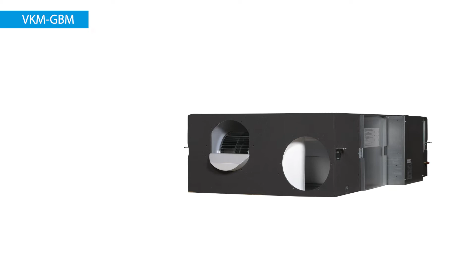Another product included in our commercial ventilation portfolio is the VKM GBM. It's also a made-to-stock standardized solution consisting of 3 sizes corresponding to airflow from 500 to 1,000 cubic meters per hour. It is a compact solution which in one casing contains the ventilation solution similar to what we saw in VAM, with a similar heat exchanger, a DX coil for heating and cooling, post-heating and cooling, but also a humidification device which allows control of the humidity of the fresh air supplied to the building.